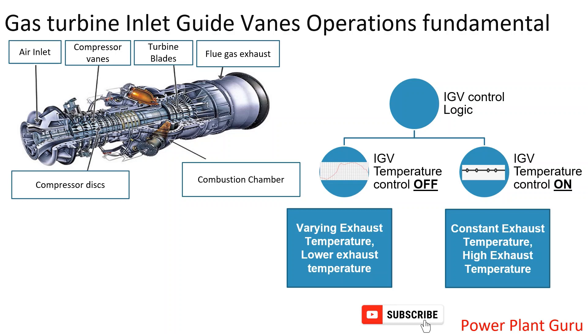The IGV follows a very complex logic here. In simple terms, it maximizes exhaust temperature — but more precisely, it monitors the ISO firing temperature. It maintains the maximum firing temperature as constant, and accordingly you get the highest possible temperature in the exhaust gases.